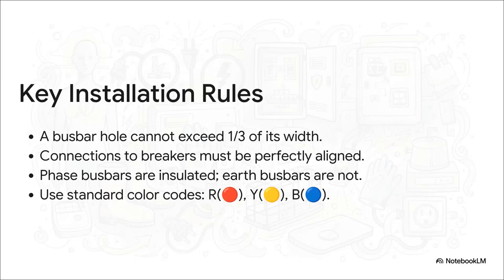And you can see how these big ideas translate into very real, specific rules. You can't drill a hole in a busbar bigger than a third of its width, because it compromises its strength. Connections have to be perfectly aligned to prevent dangerous vibrations. Insulate the live parts, but the earth busbar has to connect directly to the panel's metal body for safety. Even the color codes - red, yellow, blue - are a critical part of this blueprint, making sure a technician knows exactly what they're dealing with.